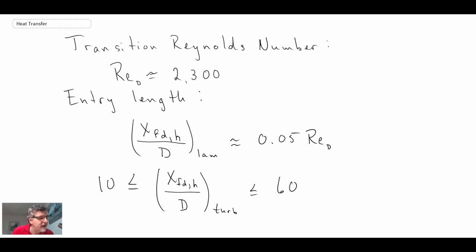Quite often in flow metering applications, they'll say you need to have 10 pipe diameters upstream or downstream of a flow meter, and so that would kind of be agreeing with this. You might have pipe flow coming along and then you have an elbow. You want to make sure that you go at least 10 diameters...